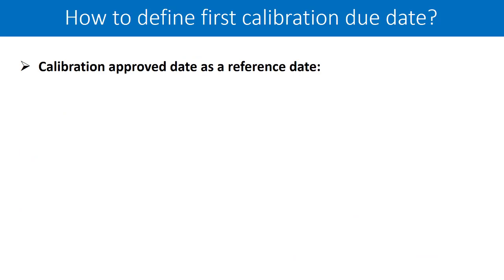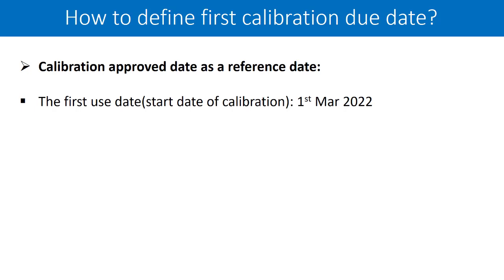Which one should be your next calibration due date? Let us talk about the calibration approval date as a reference date. You have approved your calibration data — I think this could be a good starting point: everything is perfectly executed, the data is reviewed by quality assurance, and we set this as time zero — our reference date — to calculate the next calibration due date, perhaps at 6 months. Let us first review the complete dates again. The first use date is your calibration start date.